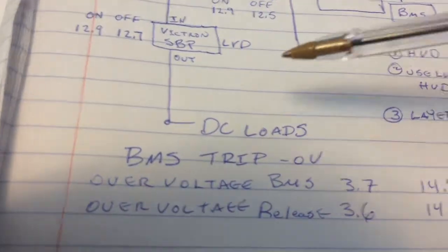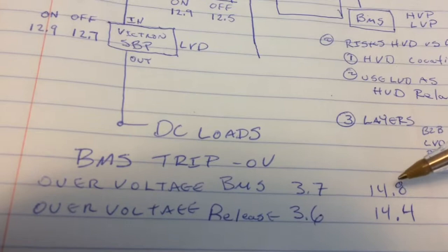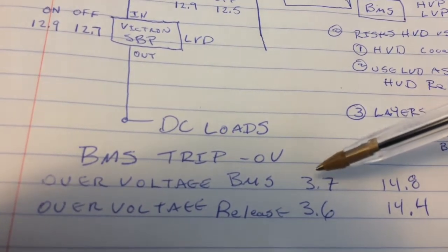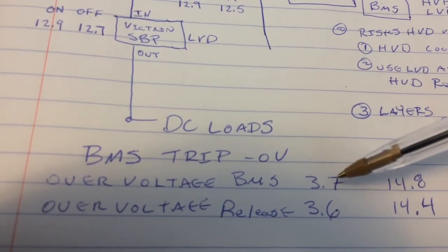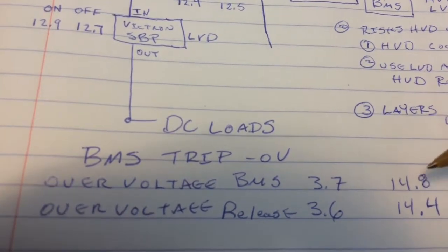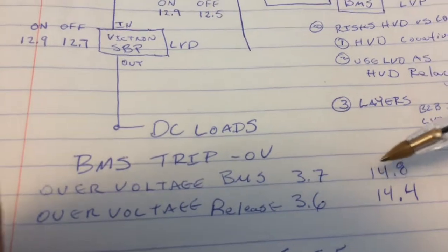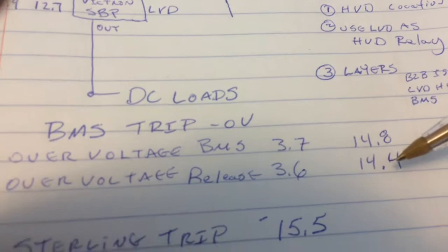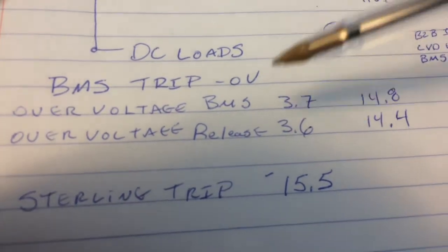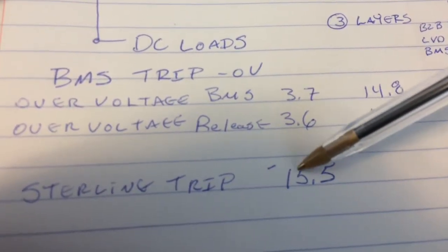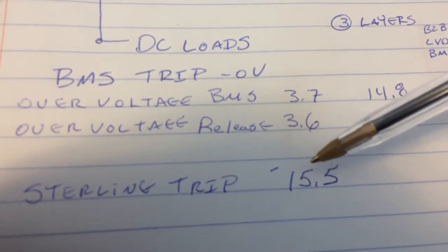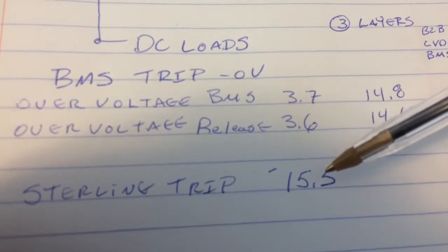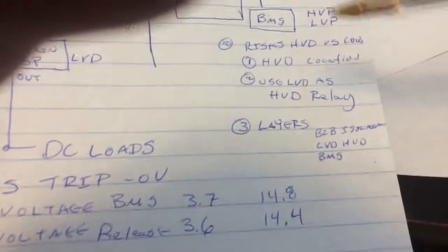So what right now my BMS is set to trigger for over voltage at 3.7 cell level over voltage and a 14.8 pack level. And then it recovers at 3.6 and 14.4. The Sterling right now, just out of the box, is set to trip at 15.5. Okay. So that does give you a little bit of extra level of protection.